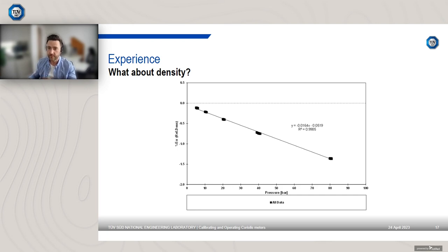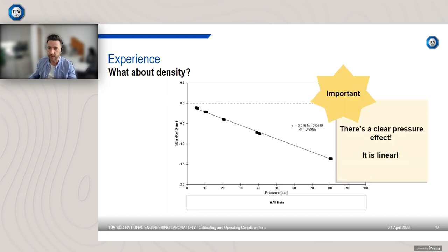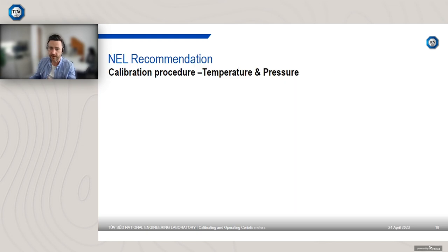You can see that the pressure effect is fairly significant again as well. So we're operating up to 80 bar. This is the reference density, and we're underreading by approximately 1.5%, so fairly significant. So it's a clear pressure effect, but thankfully once again it is linear, so that is good news. Linear means it can be easily corrected. You don't want an exponential correction, for example, or a third or fourth order polynomial. A nice linear correction is easy to correct and can be extrapolated.